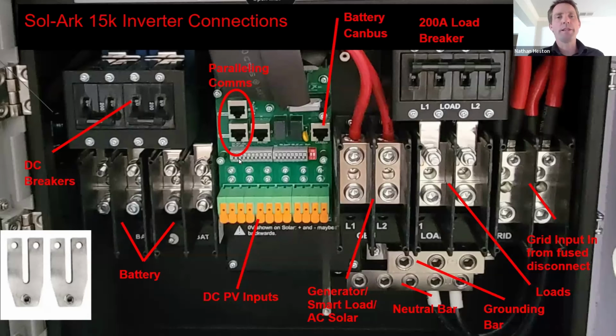Now I'm pointing out the paralleling comms connections there. If you're going to parallel multiple Sol-Ark inverters, you're going to daisy chain from one inverter to the next and then back to the first one. The CAN bus port for the batteries, where you would connect that SimpliPhi 6.6 battery stack, you just have a single battery home run coming to this CAN bus port here to have communications. Of course, the gen port that we've been talking about is here on the left. You've got your neutral bar at the bottom and then your grounding bar just above that. And then this load with your 200 amp load breaker there coming out in the middle. And then this connection on the right side is the grid port.